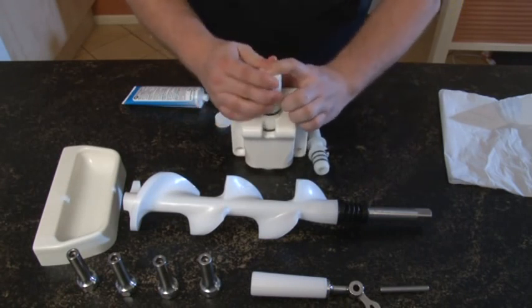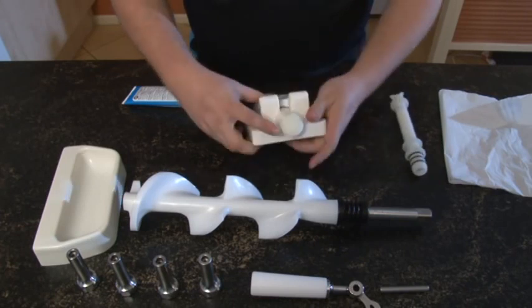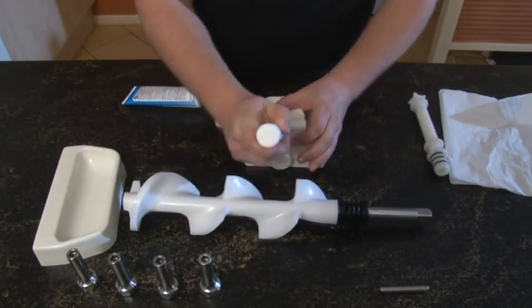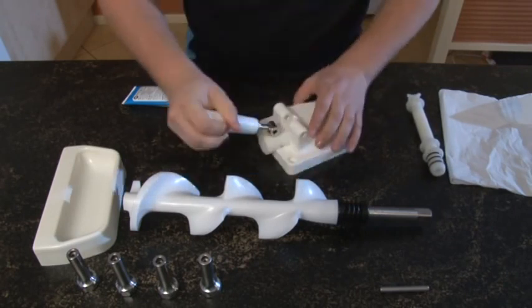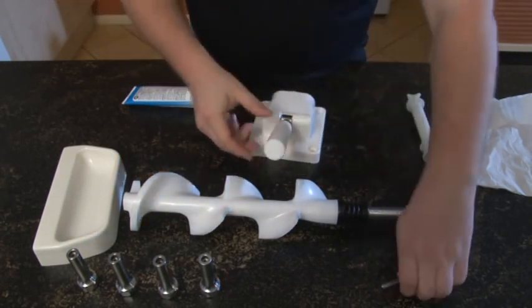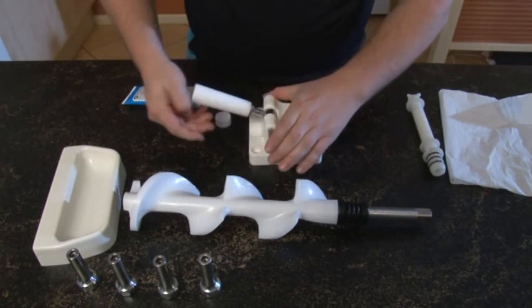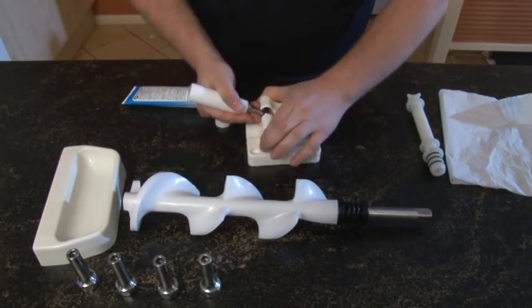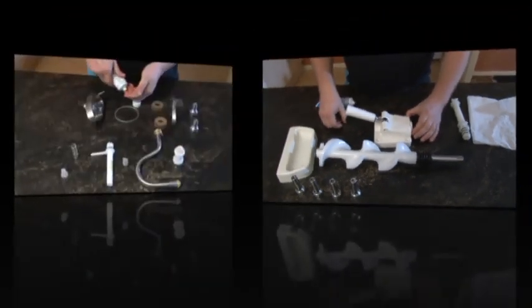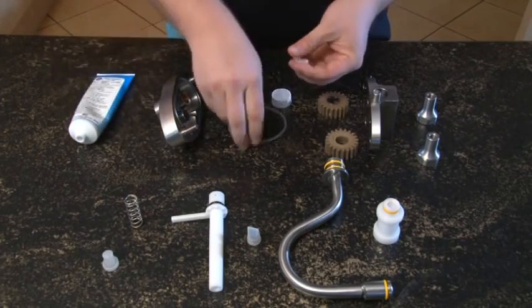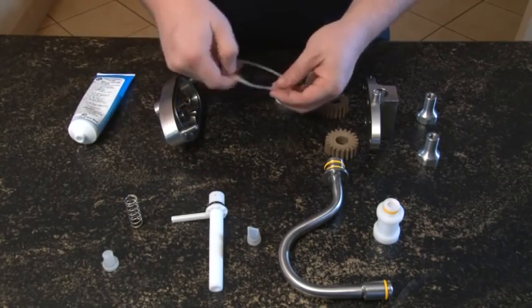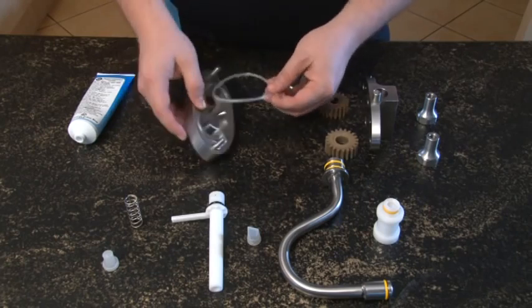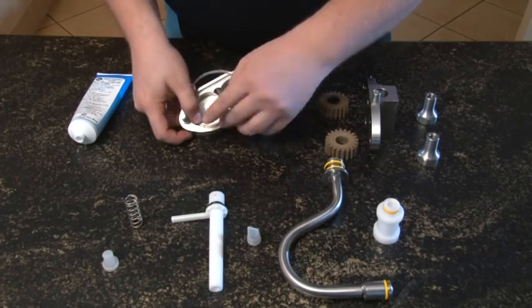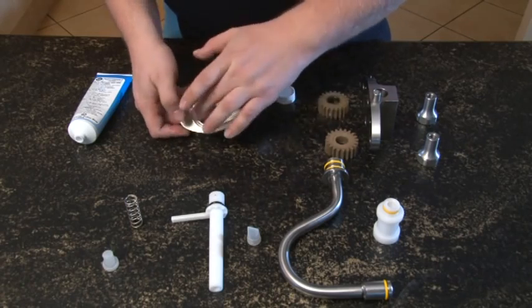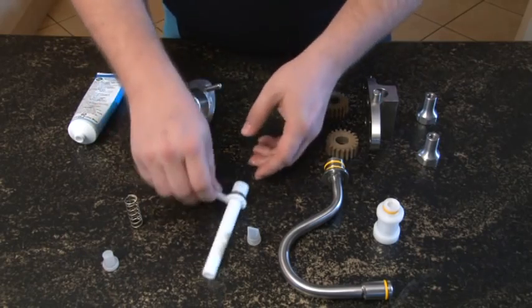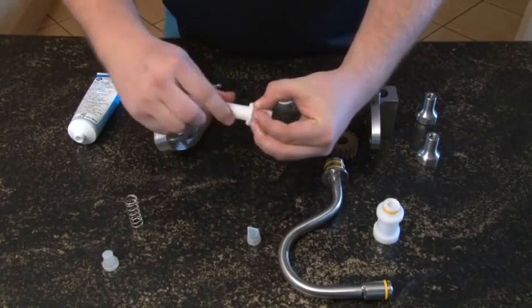Insert the plunger into the dispense head, add the crank handle and secure with the pin. The plunger fits quite tightly and gentle force is required to place it properly. In the case of the pump machine, lubricate the O-ring quite generously and place into the groove. With remaining lubricant on your fingers, lubricate all other O-rings.